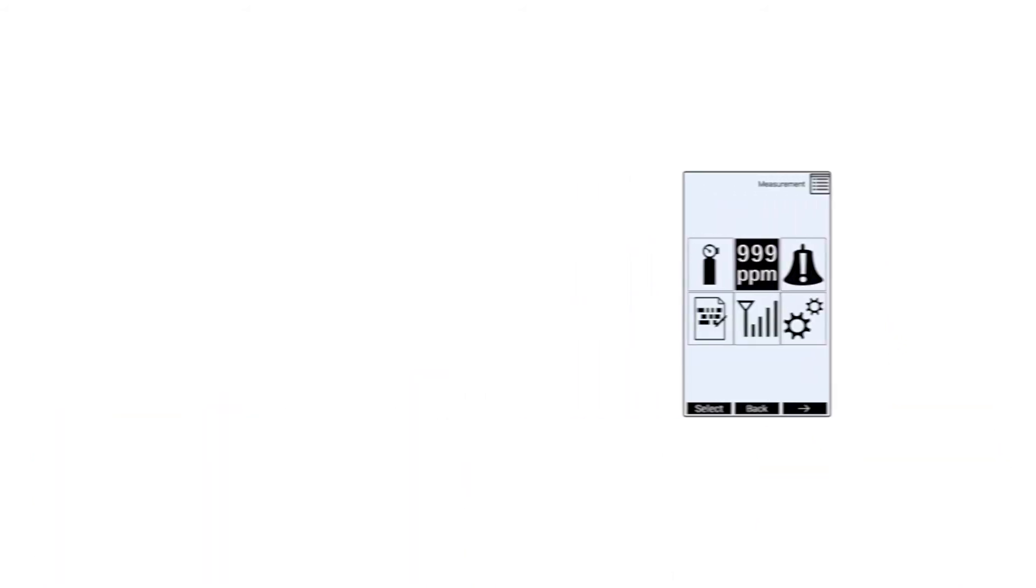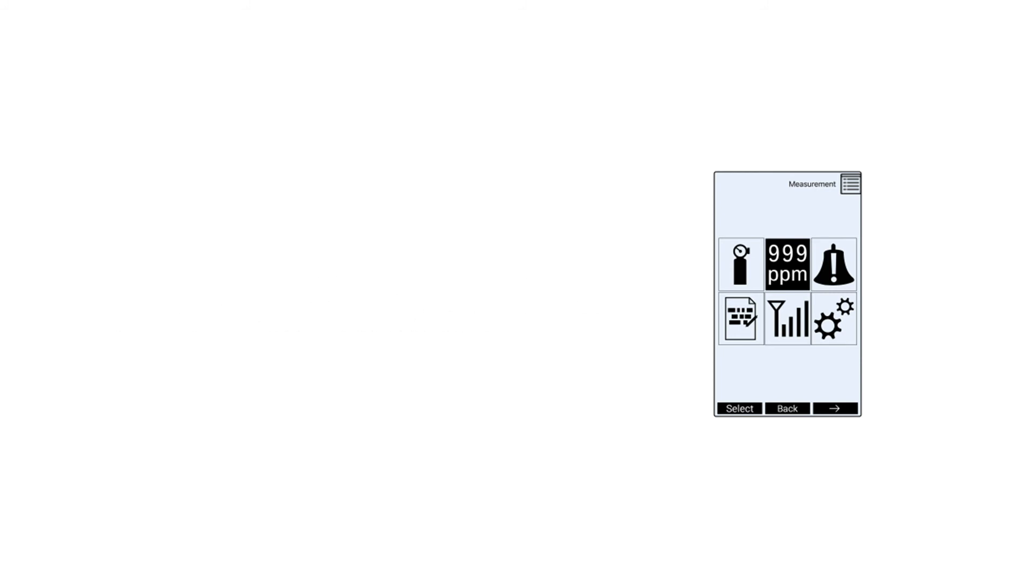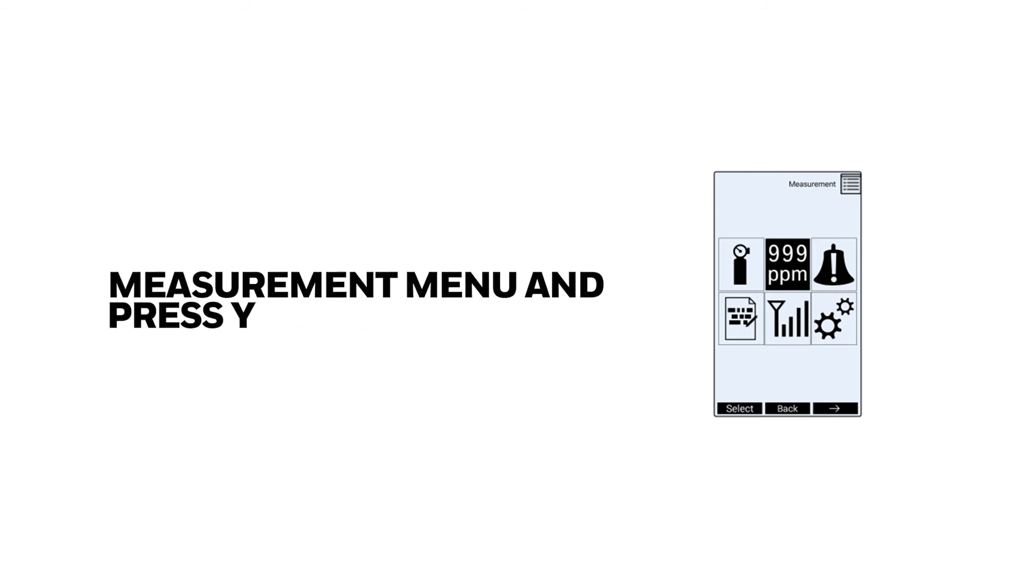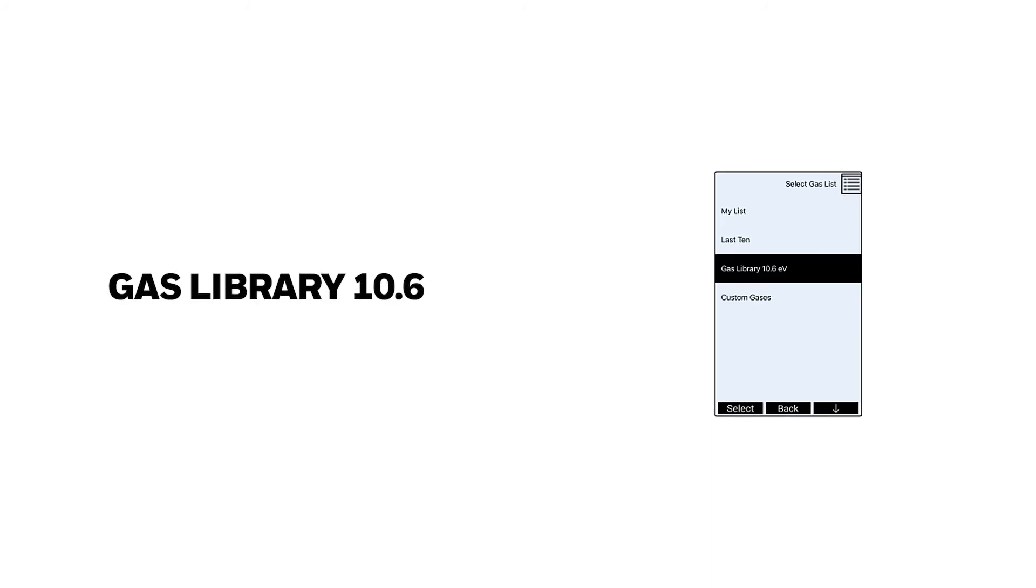Enter in the configuration menus by pressing and holding the On and the N button at the same time. Select the measurement menu and press the Y button to enter. Select change measure gas and select VOC option, gas library 10.6, and select the target gas.